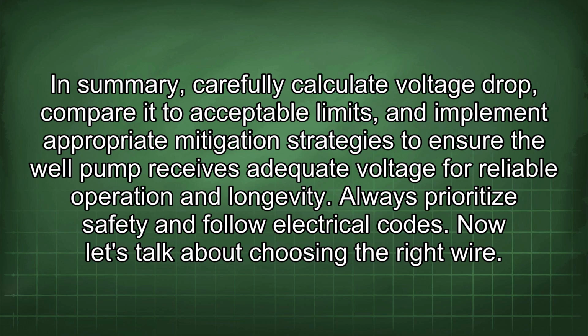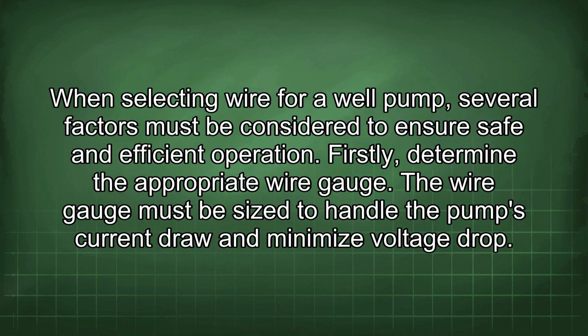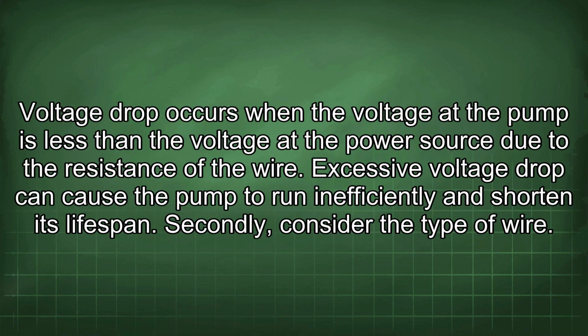Now let's talk about choosing the right wire. When selecting wire for a well pump, several factors must be considered to ensure safe and efficient operation. Firstly, determine the appropriate wire gauge. The wire gauge must be sized to handle the pump's current draw and minimize voltage drop. Voltage drop occurs when the voltage at the pump is less than the voltage at the power source due to the resistance of the wire. Excessive voltage drop can cause the pump to run inefficiently and shorten its lifespan.